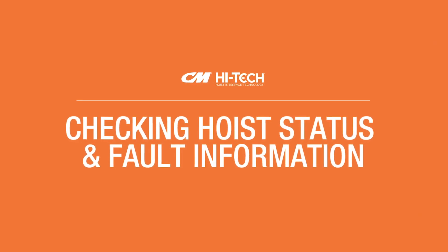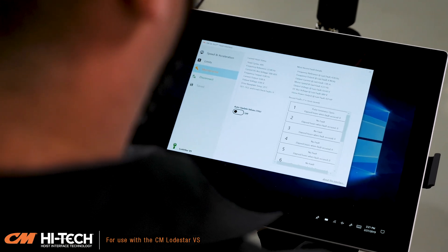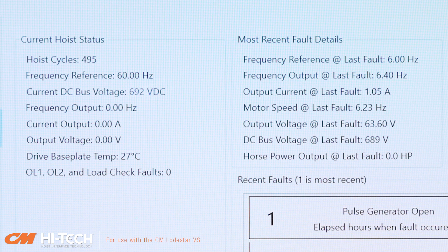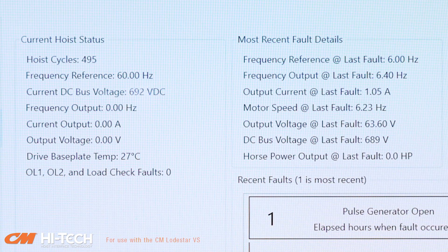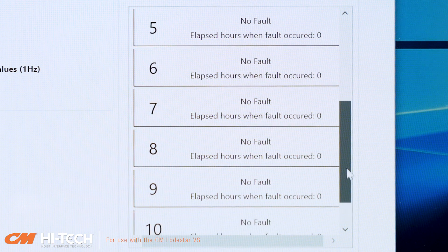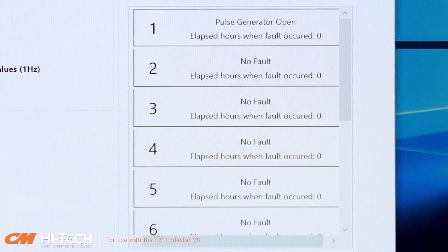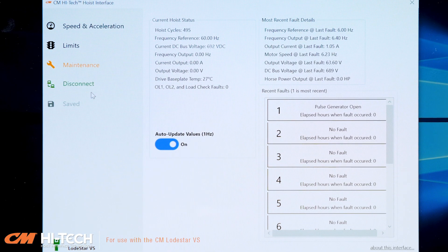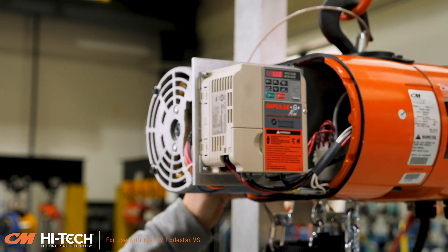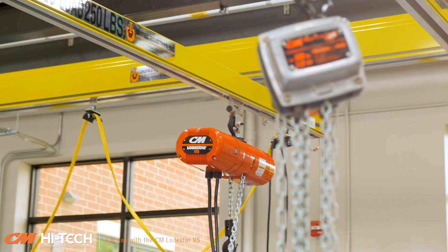Checking Hoist Status and Fault Information. Within the CM Hi-Tech interface, you can easily access hoist status and fault information. If you click on the Maintenance tab, you'll see two sections. The first is Current Hoist Status, which shows comprehensive hoist status information, including stop and start cycles, motor run time, DC bus voltage, as well as over-temp and over-current events. The other section will show hoist fault information, including errors and failures. This is extremely useful because it allows you to easily access onboard diagnostics, so you can identify and resolve issues within preventative maintenance before they become bigger problems. CM Hi-Tech has built-in error prevention, ensuring the hoist is programmed correctly by rejecting incorrect parameters and prompting you to make corrections before programming is complete.